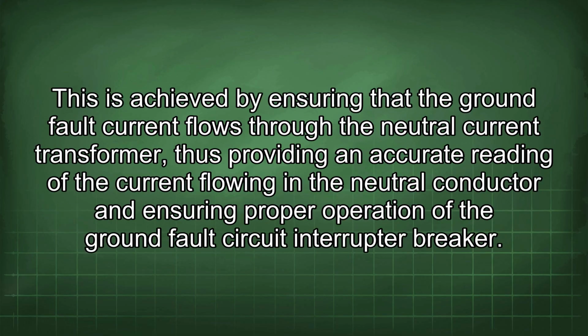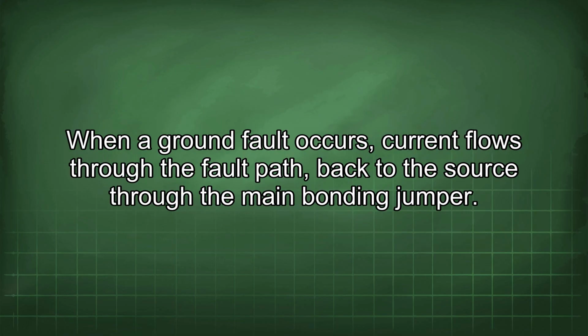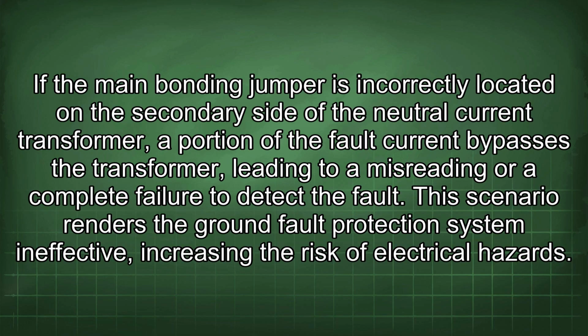This is achieved by ensuring that the ground fault current flows through the neutral current transformer, thus providing an accurate reading of the current flowing in the neutral conductor and ensuring proper operation of the ground fault circuit interrupter breaker. When a ground fault occurs, current flows through the fault path back to the source through the main bonding jumper. If the main bonding jumper is incorrectly located on the secondary side of the neutral current transformer, a portion of the fault current bypasses the transformer, leading to a misreading or a complete failure to detect the fault. This scenario renders the ground fault protection system ineffective, increasing the risk of electrical hazards.